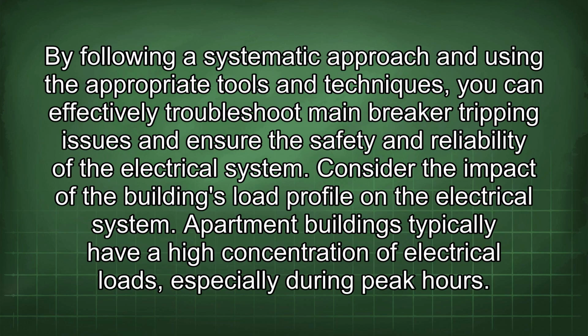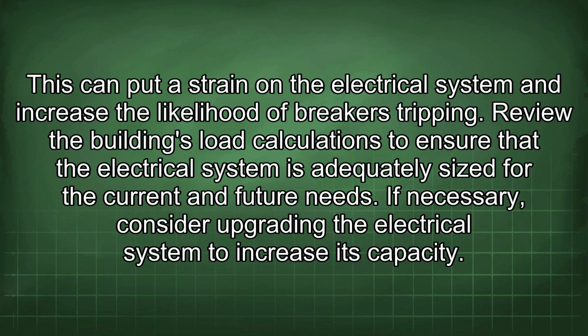By following a systematic approach and using the appropriate tools and techniques, you can effectively troubleshoot main breaker tripping issues and ensure the safety and reliability of the electrical system. Consider the impact of the building's load profile on the electrical system. Apartment buildings typically have a high concentration of electrical loads, especially during peak hours. This can put a strain on the electrical system and increase the likelihood of breakers tripping.